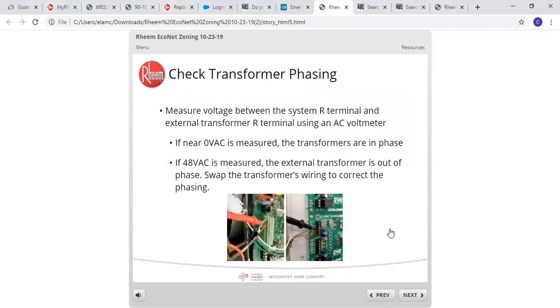We'll go over checking the transformer phasing. So measure the voltage between the system R terminal and the external transformer R terminal using an AC voltmeter. If near 0 VAC is measured, the transformers are in phase. If 48 VAC is measured, the external transformer is out of phase. Swap the transformer's wiring to correct the phasing.